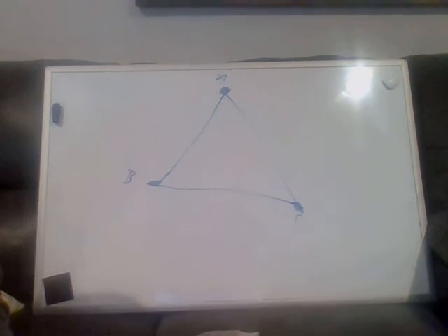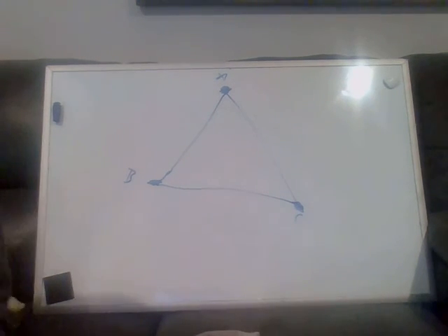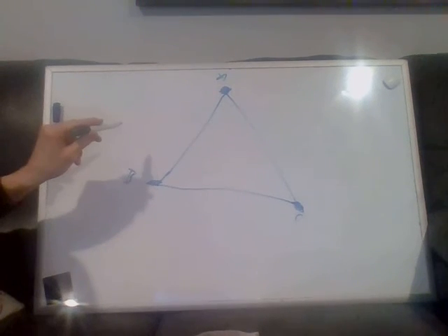So then, if we have one of the phases fault out, how then can a breaker trip? Because even though it doesn't really matter, it can be a problem for various reasons. You don't want, if another one were to fault out, you might have a big flash or something like that. Well, it's simple. We have a zigzag transformer at the substation or something like that, connected to a ground fault relay.